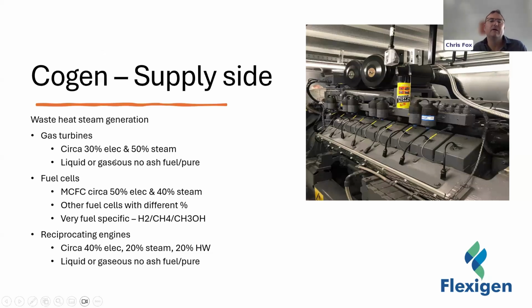In terms of steam, same thing - it all depends on pressure, superheat and so on. But a rough figure would be you could probably produce 40 to 50% steam from the exhaust. How that's done is you put in a big heat exchanger with a fancy name called HRSG, which takes the hot exhaust from the turbine and raises steam.